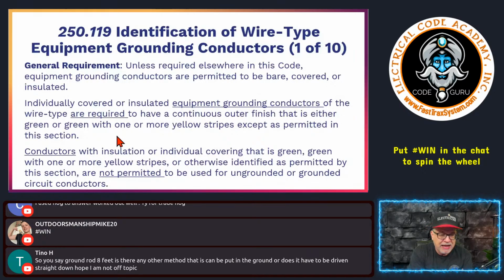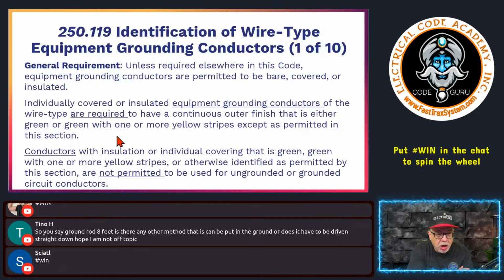If I have a green, then if I have another one, let's say for isolated ground, we would have a green with a yellow stripe to signify there's a difference. But that's important. Now, could you have a bare in a lot of products? Absolutely, you could. Just remember, when it is insulated, or the equipment ground is covered, other than, for example, where it's permitted in a cable assembly, like an SER or something like that, which is going to restrict its use to above ground only, right? And so those types of applications.